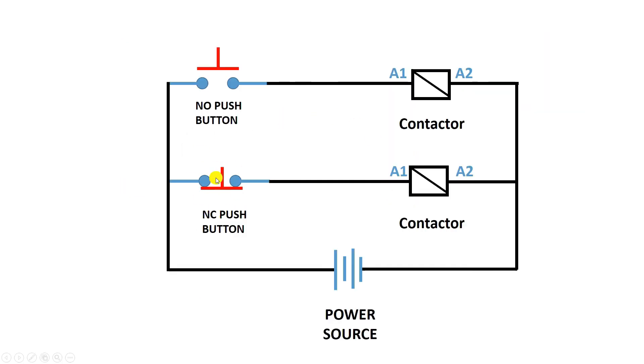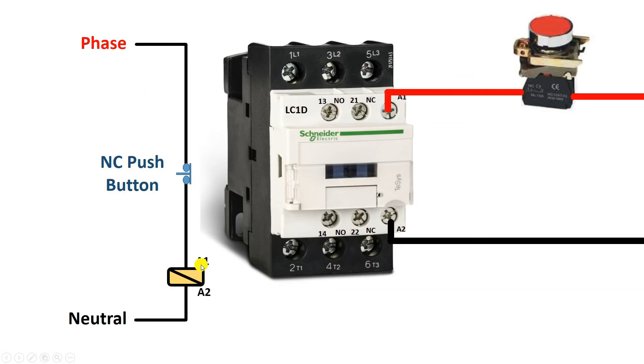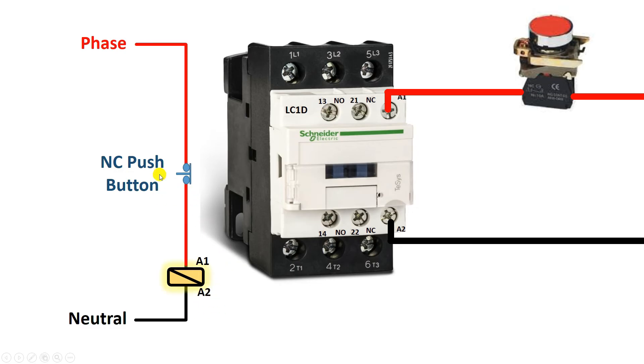Here an NC push button is connected with the contactor. What happens when this push button is connected — let's understand. I connected the NC push button in series with the contactor. In this condition, if you do not press this push button, the NC push button lets the power supply always flow, so the contactor remains on. But when you press this push button, the circuit will break, and due to the break in the circuit your contactor turns off. As long as you press this push button, the contactor is in off condition. On releasing it, the contactor will again turn on, because power supply from here is now going to this contactor.